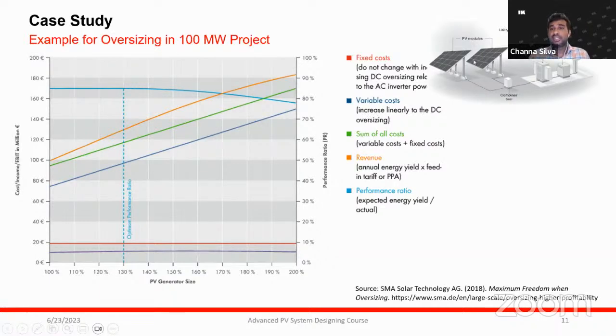Variable cost, on the other hand, is the DC side system, which can vary because of adding more panels. You may require more parallel strings, additional DC cables, additional mounting structure, additional land space, and labor requirements - all of these can be variable costs. When you do oversizing, that increases linearly, so the total sum of cost also varies with the oversizing factor.